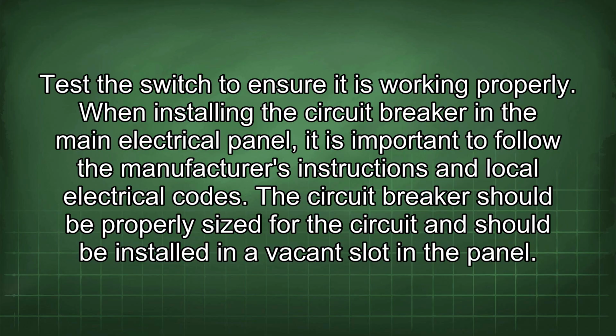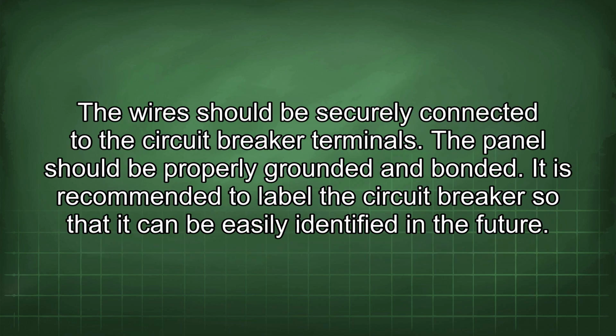When installing the circuit breaker in the main electrical panel, it is important to follow the manufacturer's instructions and local electrical codes. The circuit breaker should be properly sized for the circuit and should be installed in a vacant slot in the panel. The wires should be securely connected to the circuit breaker terminals. The panel should be properly grounded and bonded. It is recommended to label the circuit breaker so that it can be easily identified in the future.